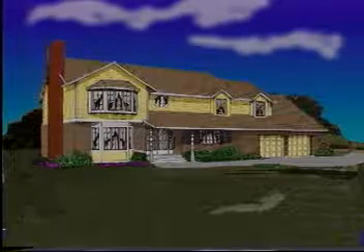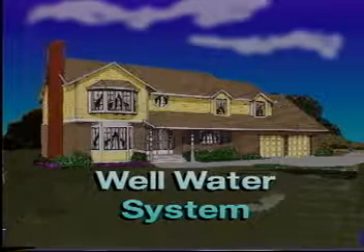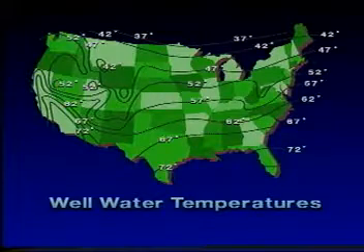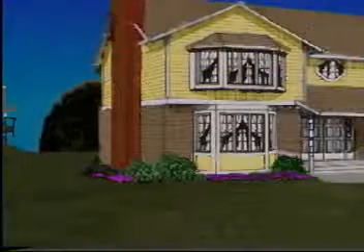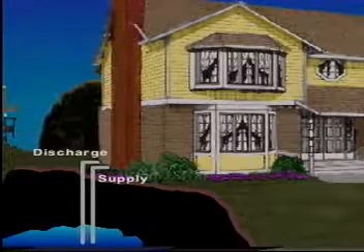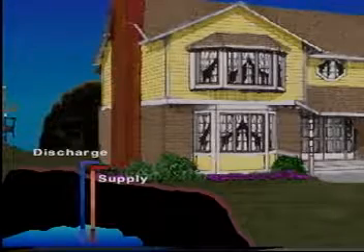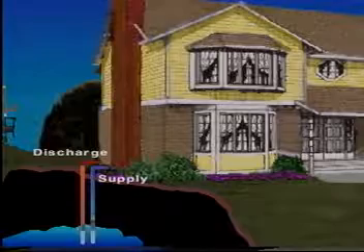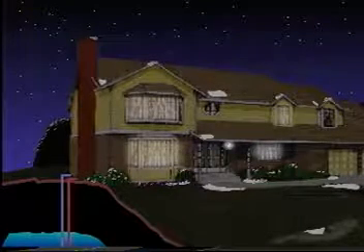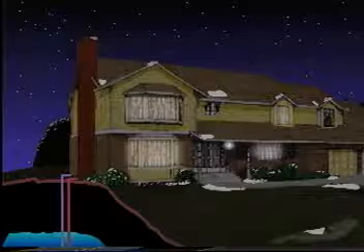Another important application of water source heat pumps is using well water to heat and cool residences and commercial buildings. The water source heat pump has for years been the most efficient and therefore the most economical system to operate. The reason for this is well water at 30 feet keeps a constant temperature within a single degree throughout the year. In many parts of the country, this groundwater is easily accessible at moderate depths. With the system, a supply well and a discharge well are drilled. In the winter, heat is absorbed from the water coming from the supply well, and the groundwater is then discharged to a return well. During the summer, heat is discharged to the return well. Due to the constant mild temperatures of the ground, even when there are extreme temperatures outside, a water source heat pump maintains its superior efficiencies of operation. It is also important to note that at no time is the groundwater exposed to the atmosphere.